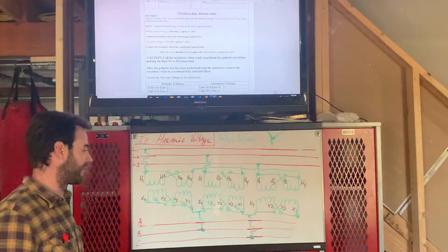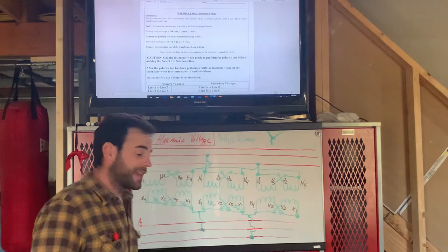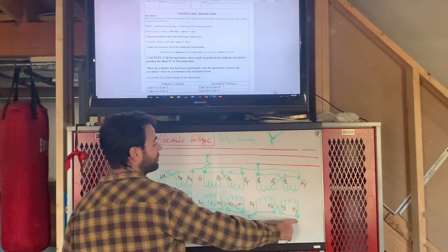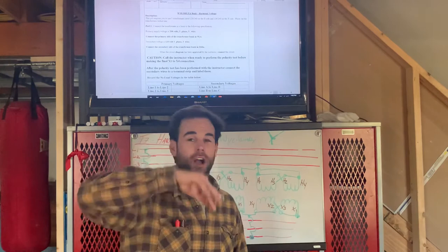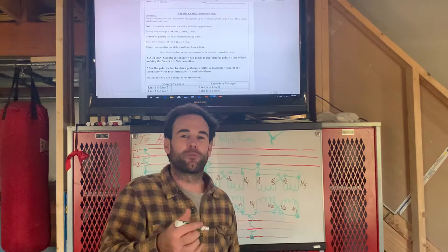give voltages anywhere from 120 volts to 160 volts. You wouldn't think of connecting those two wires. Back in the day, before they had meters that could measure frequency, they would connect a light bulb to those two points because they figured if it was 60 hertz power, it would turn a light bulb on and stay on. Anything other than that, in our case 180 hertz, because the sine wave is changing polarity three times as much compared to 60 hertz power, is changing polarity so frequently it doesn't have the same electrical pressure as 60 hertz power does.